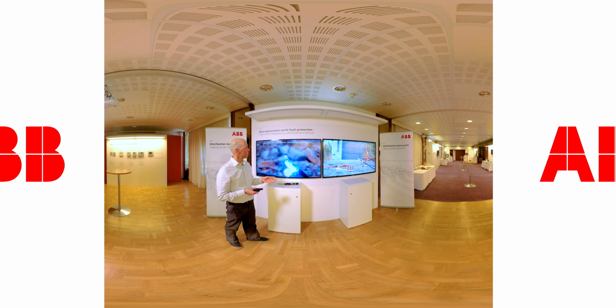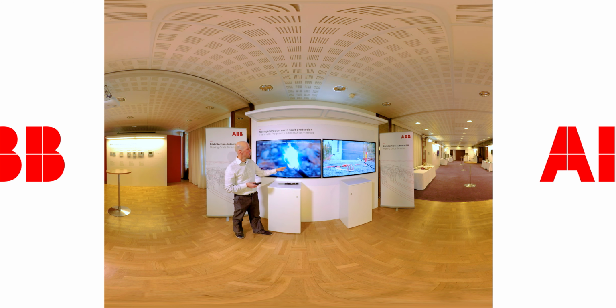of this particular fault type comes from the fact that when we look at what is happening at the fault location in slow motion, you can see that this fault is very temporary. The fault is in fact composed of a series of very short duration insulation breakdowns, and during this time of insulation breakdowns, what protection sees is only a very short duration of current flowing in the system.